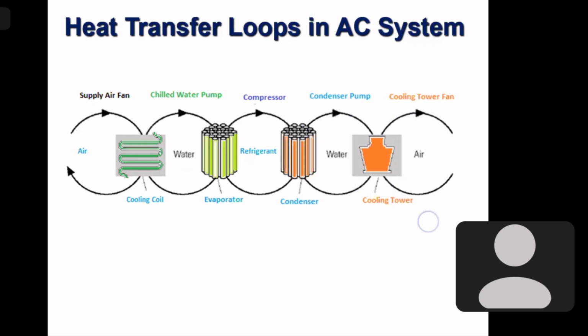So heat from the room comes to the cooling coil, then from there it goes to the evaporator, from there it goes to the condenser, and then the heat is taken out by water and finally dissipated into the atmosphere by the cooling tower, with hot air from the cooling tower. So this is how the heat moves from the room to the atmosphere through the cooling tower via the cooling coil of the air handling unit, then through the evaporator coil, that is the chilled water coil, then to the refrigerant, then to the condenser coil, then to the condenser cooling water, then to the cooling tower, and then finally to the atmosphere. This is how the heat transfer takes place.